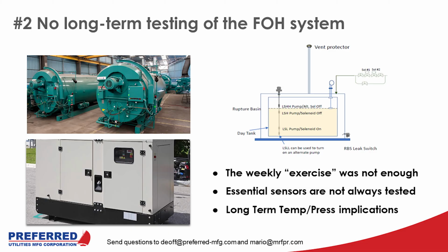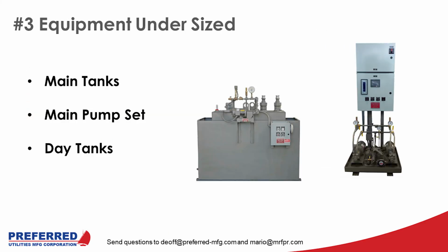Number three on our list is equipment undersized. We have been speaking about auxiliary generators so far, but boilers are essential components in multiple sites in Puerto Rico. Steam is utilized for hot water, for reheat coils, and for sterilization, and boilers utilize diesel fuel oil number two. So, since we have the boilers typically using diesel oil number two, but now we have the gensets operating full time, some facilities share the main fuel oil tank and they share the main pump between the boiler and the auxiliary genset.